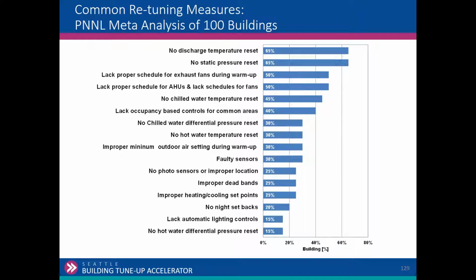Improper dead bands, heating and cooling set points, no night setbacks. Again, keeping in mind the system types. Lack of automatic lighting controls. Well, that's generally a capital measure, but it may make sense. Wow, you have no occupancy sensors in this building, or no lighting controls, or the outside lights are on all night. So there may be something there. And then hot water pressure differential reset, fairly small. But again, we can look at the cream on the top when we think about where the savings are going to occur.